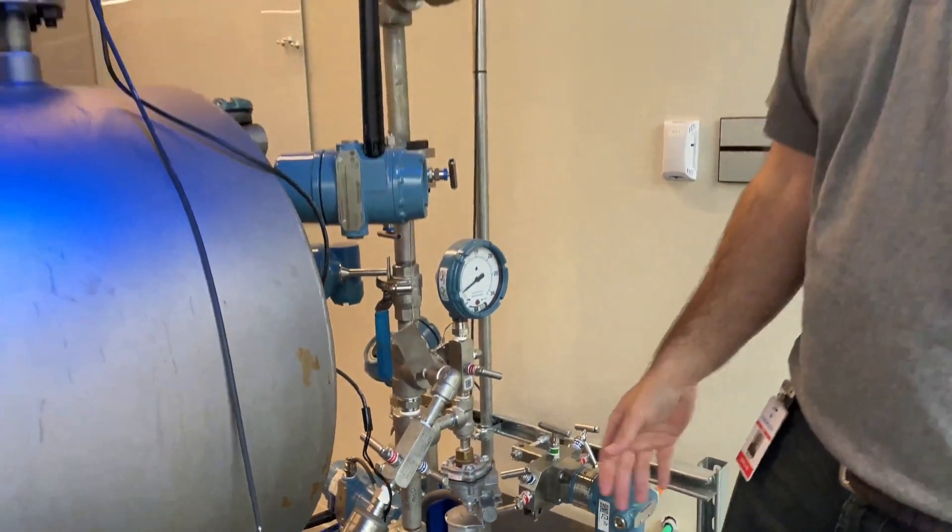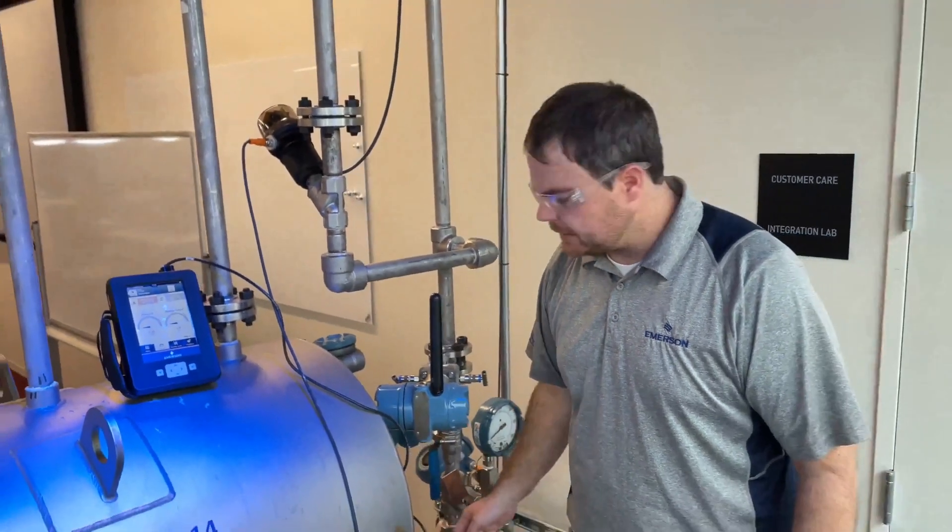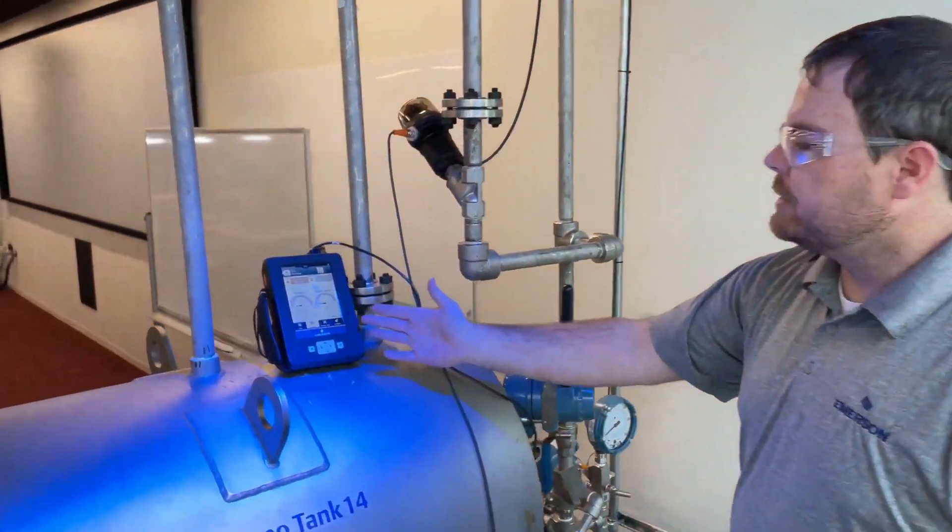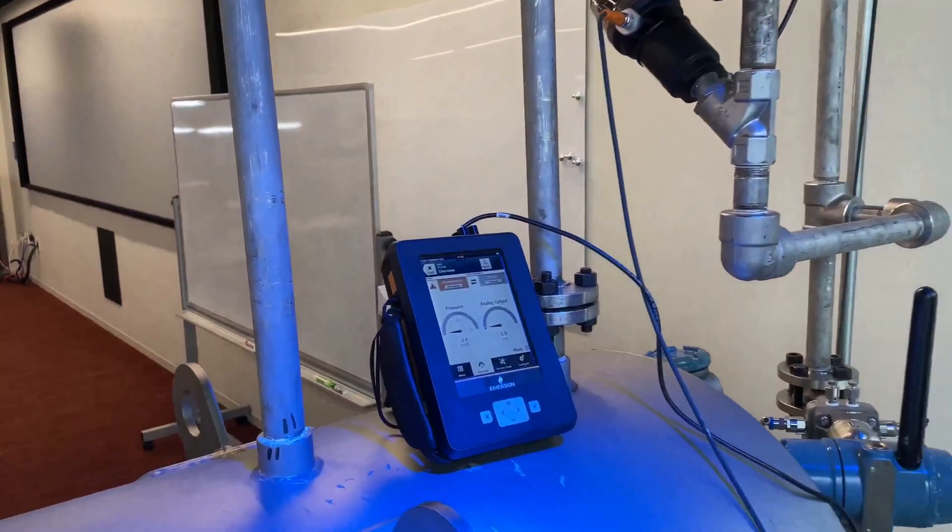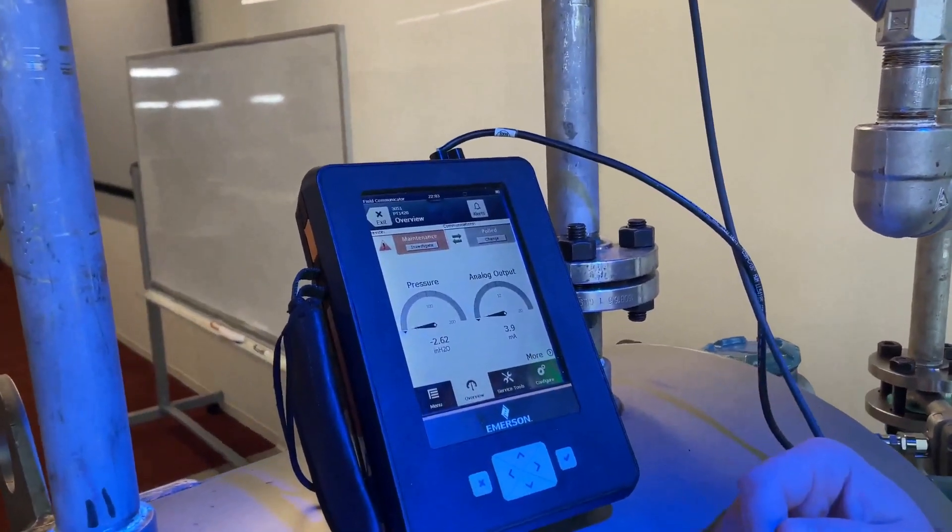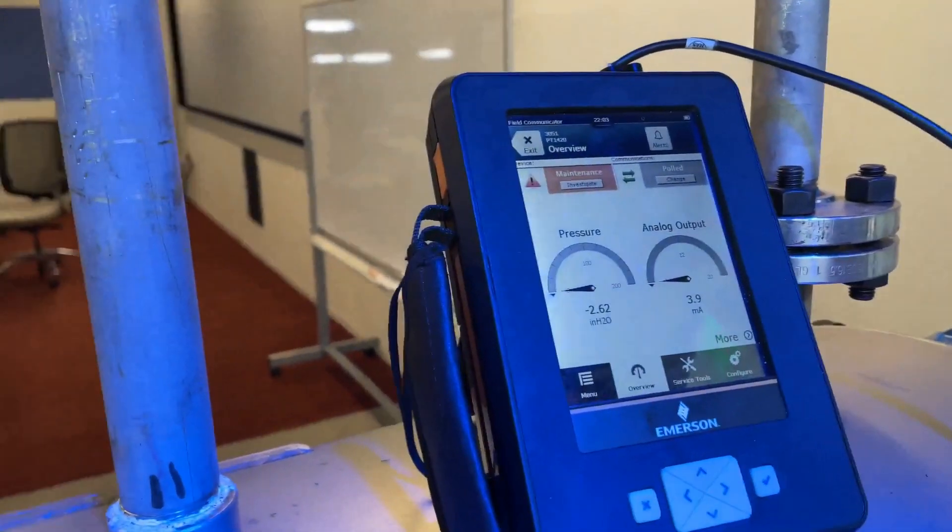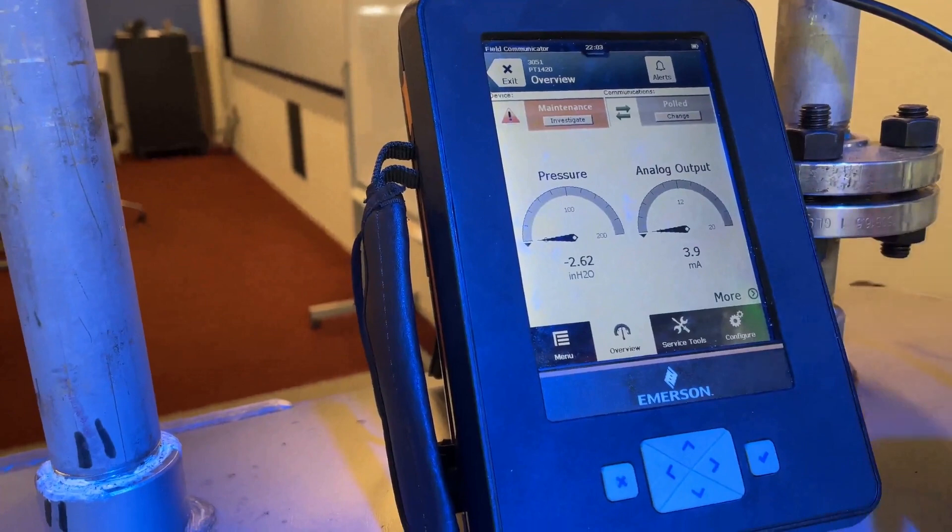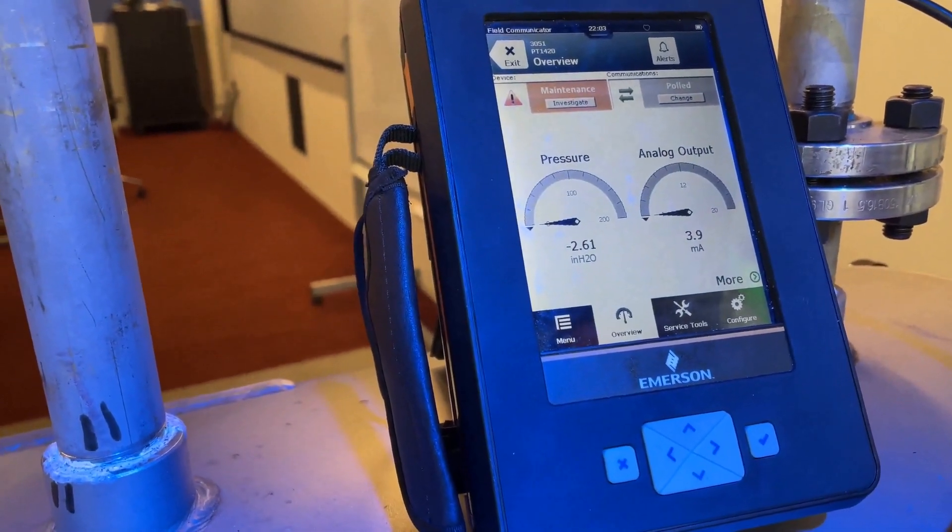So to perform this, make sure you are vented. As you can see from our Trex screens, just by mounting this transmitter upside down, we have induced a pressure as well as changed our milliamp output.